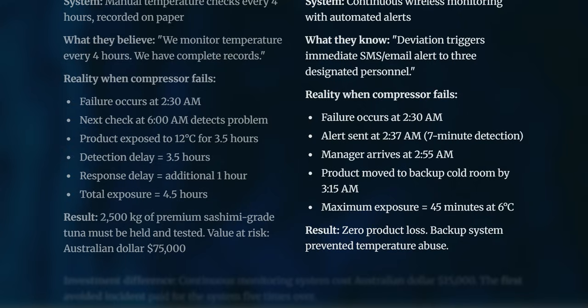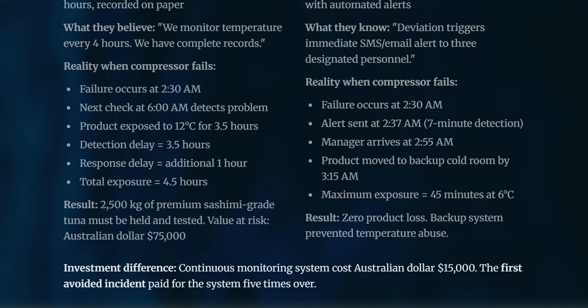In the first case, the risk was a product worth 75,000 Australian dollars, but with the new system they haven't risked anything, and the backup system prevented the temperature excursion. Now let's look at the investment that prevented that $75,000 loss. The continuous monitoring system cost around $15,000 Australian dollars, and the first avoided incident paid for the system five times over. They would have lost $75,000, but instead they invested $15,000 and prevented the loss.